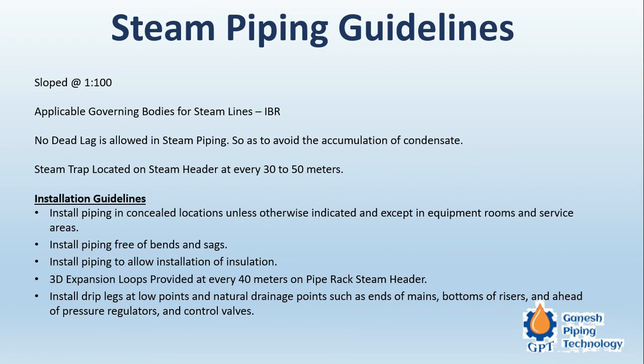Installation guidelines include: install piping in concealed locations unless otherwise indicated, except in equipment rooms and service areas. Install piping free of bends and sags — a sag creates a bow where condensate may accumulate. Install piping to allow installation of insulation with proper shoe supports. 3D expansion loops are provided at every 40 meters on pipe rack steam headers to absorb the majority of expansion and keep stresses within limits.